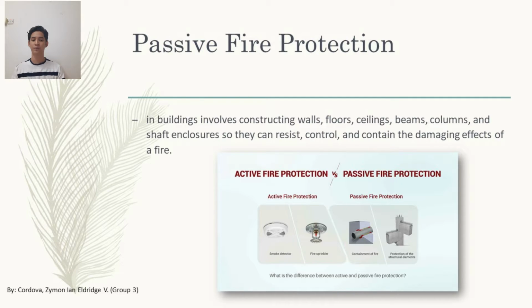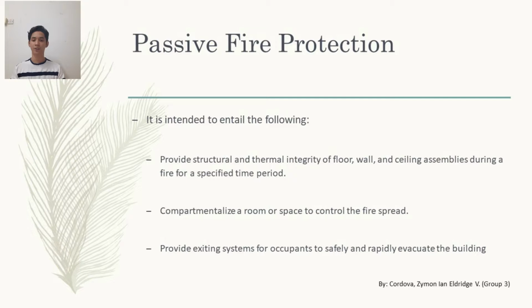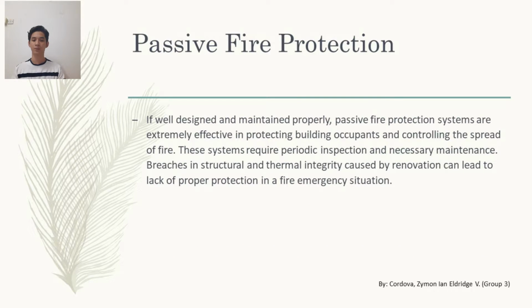The difference of active fire protection and passive fire protection is in the image below. Passive fire protection is intended to entail the following: Provide the structural and thermal integrity of floor, wall, ceiling assemblies during a fire for a specified time period. Compartmentalize a room or space to control the fire spread. Provide the exiting systems for occupants to safely and rapidly evacuate the building. If well designed and maintained properly, passive fire protection systems are extremely effective in protecting building occupants and controlling the spread of fire. The systems require periodic inspection and necessary maintenance.